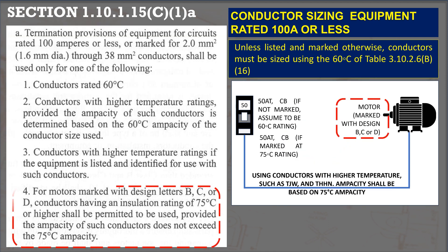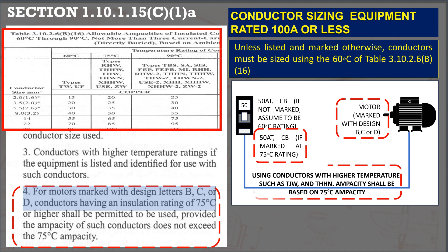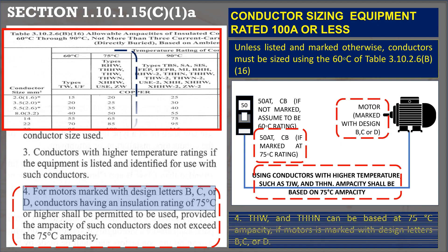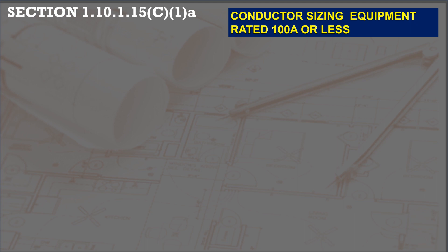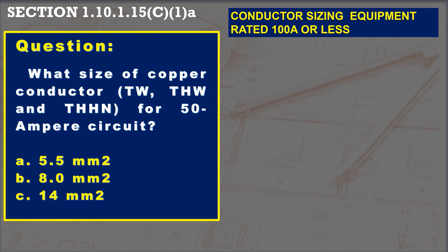When a motor is marked with design letters B, C, or D, the equipment terminal rating is considered to be 75 degrees Celsius. And if the circuit breaker is also marked at 75 degrees Celsius, conductors can be sized based on the 75 degrees Celsius column of the ampacity table.